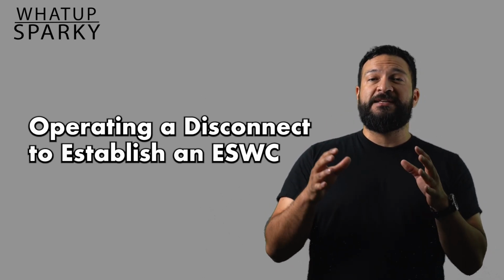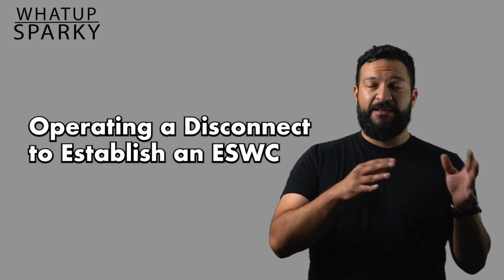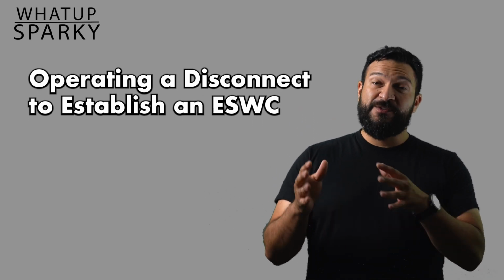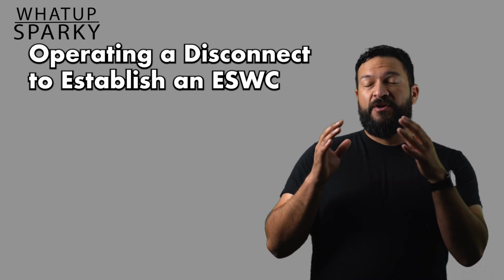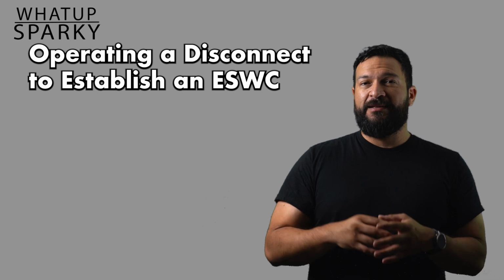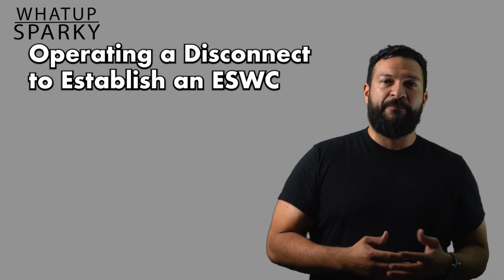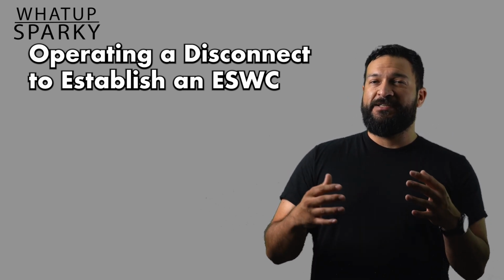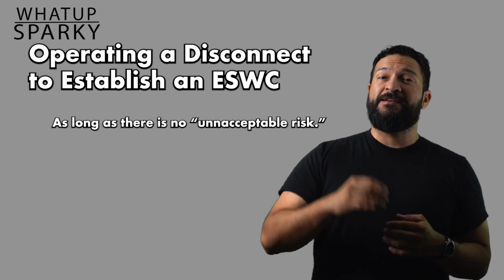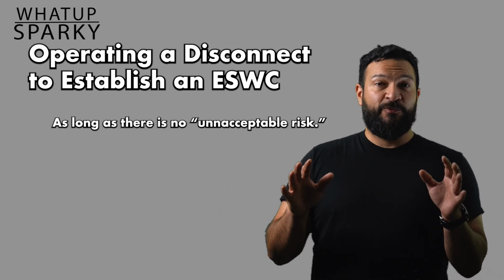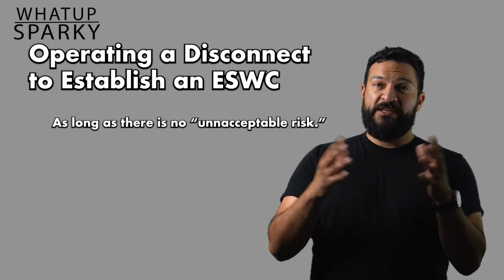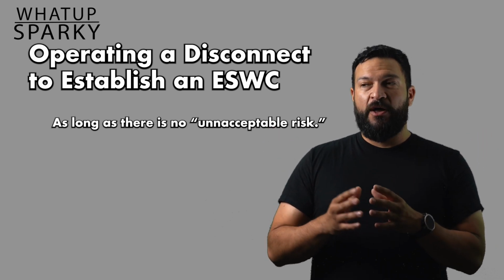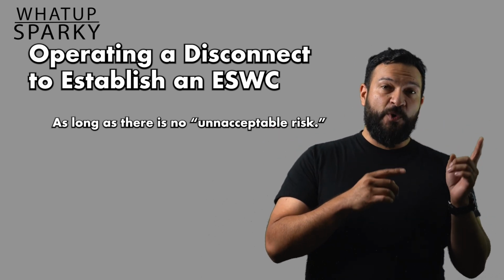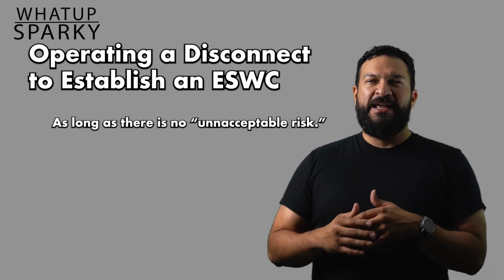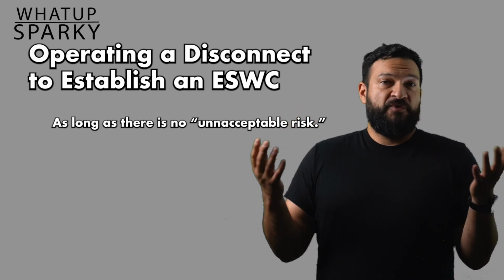So the second one is operating a disconnecting means to establish an electrically safe work condition. This one's close to the first. You're allowed to operate a disconnect like a switch or a breaker to create an electrically safe work condition as long as there's no unacceptable risk involved with that. And what defines unacceptable risk? Well, go back and check exception 1, normal operation, and if it meets that list, you're good.